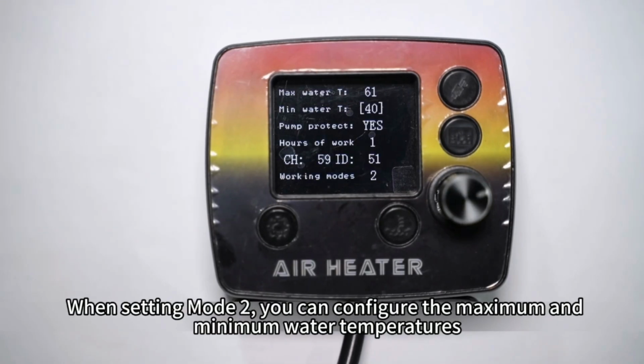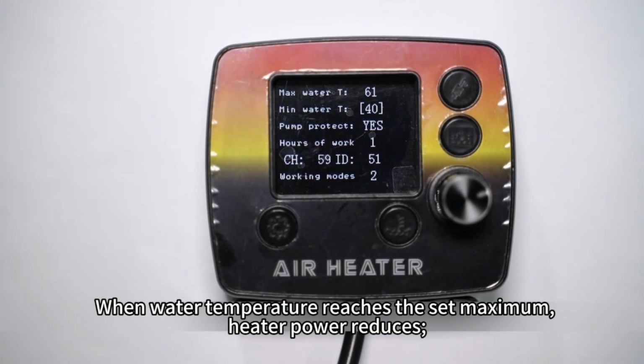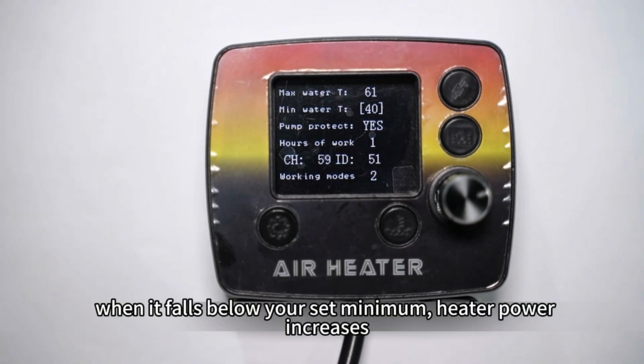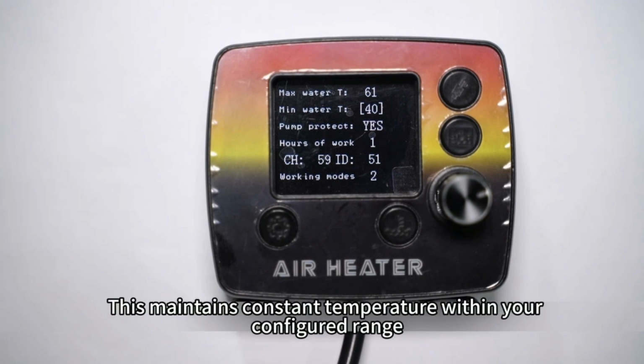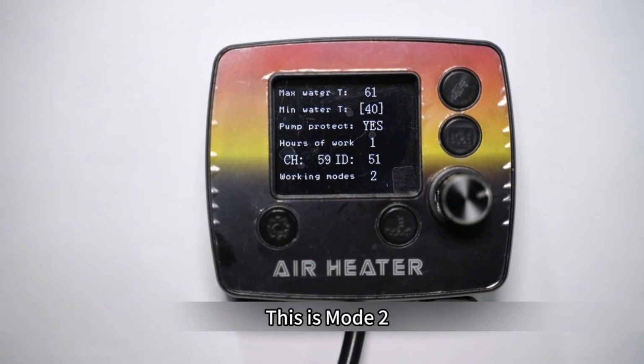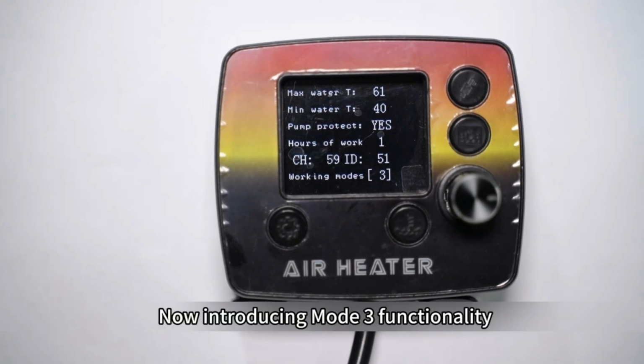When setting Mode 2, you can configure the maximum and minimum water temperatures. When water temperature reaches the set maximum, heater power reduces. When it falls below your set minimum, heater power increases. This maintains constant temperature within your configured range. This is Mode 2. Now introducing Mode 3 functionality.